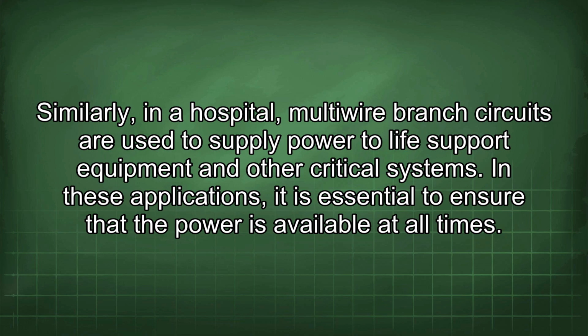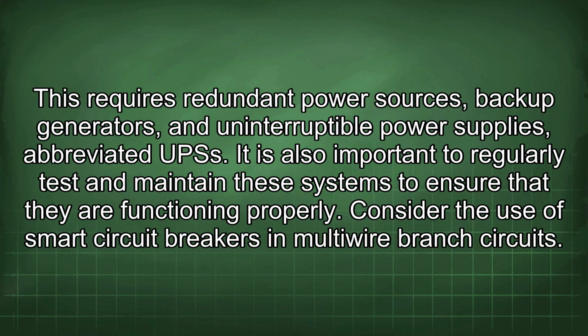Similarly, in a hospital, multi-wire branch circuits are used to supply power to life support equipment and other critical systems. In these applications, it is essential to ensure that the power is available at all times. This requires redundant power sources, backup generators, and uninterruptible power supplies, abbreviated UPS. It is also important to regularly test and maintain these systems to ensure that they are functioning properly.